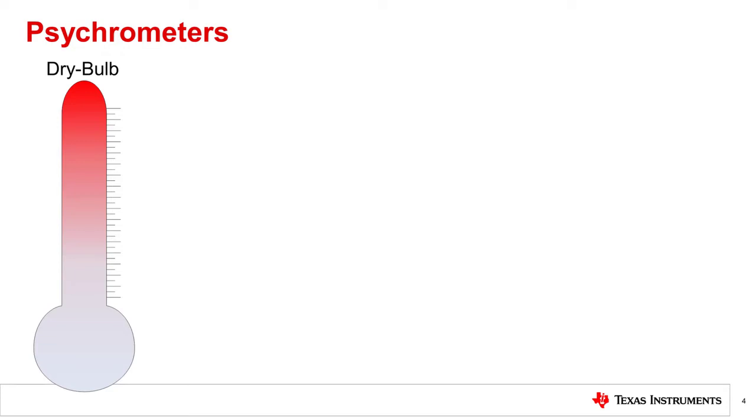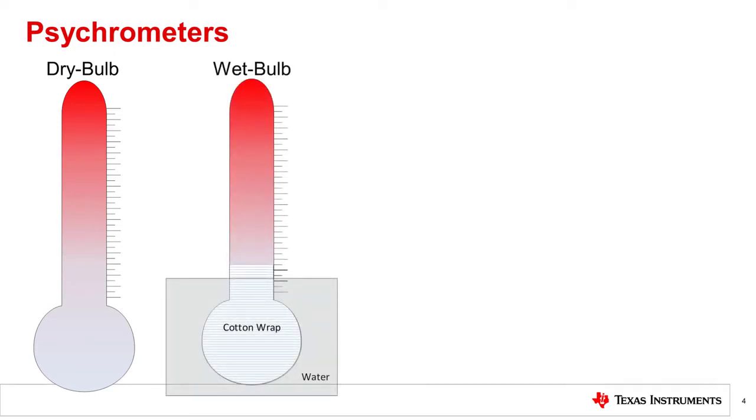As the name implies, this tool starts with a dry bulb thermometer, which is typically shielded in some way from radiation, and a wet bulb thermometer, which is wrapped in a cotton wick or sock that is wet in order to allow the effects of evaporative cooling to take place. Because one of these thermometers is being cooled by the evaporation of moisture and one is not, there will be a measurable temperature difference between the two.